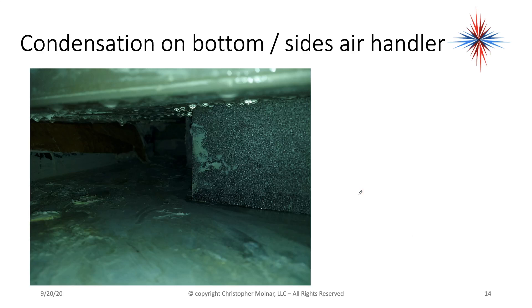Another thing you can look at as you look at air flow: if you see condensation on the bottom or the sides of the air handler. This is an air handler where it's actually dripping water, and it's not because it's leaking. Condensation on the bottom or sides of the air handler is a typical sign of low air flow. Think about a glass of ice water sitting on a kitchen counter in a humid room and how much condensation occurs on the outside of the glass. If I have an air handler that's too cold because of lack of air flow, no matter how much insulation is in that air handler, I'm going to get condensation if it's in a humid environment — for example, in an attic in Florida or a garage in Florida.